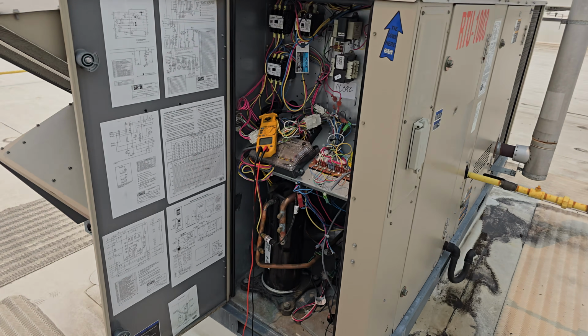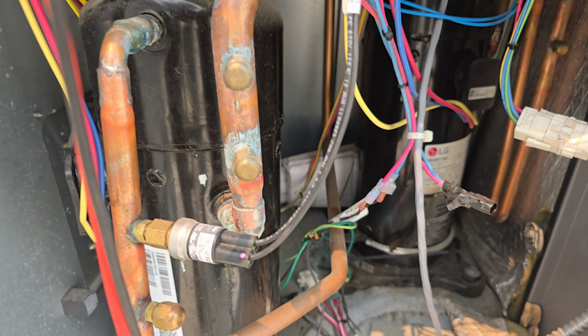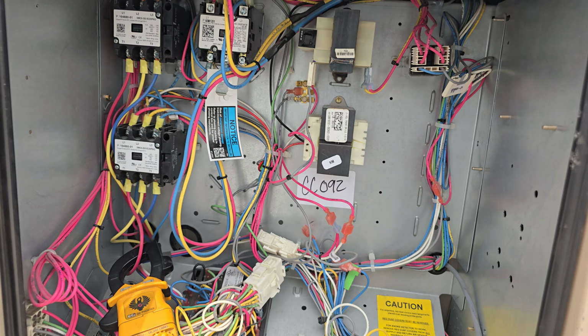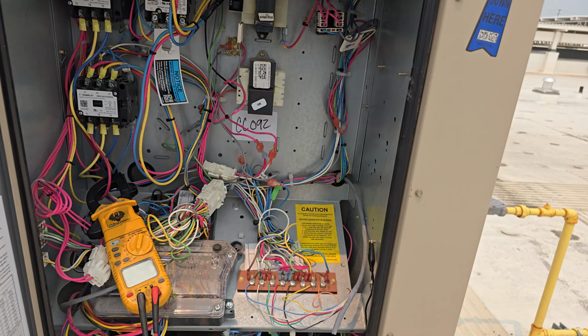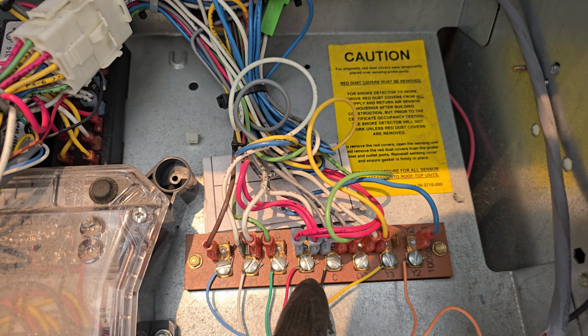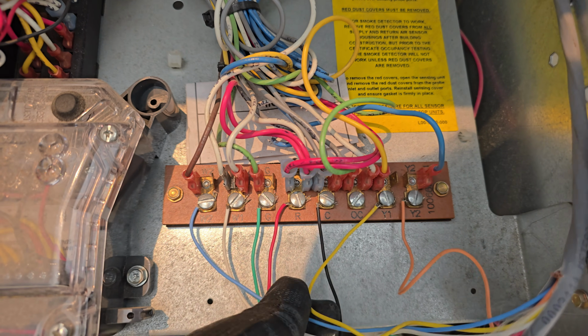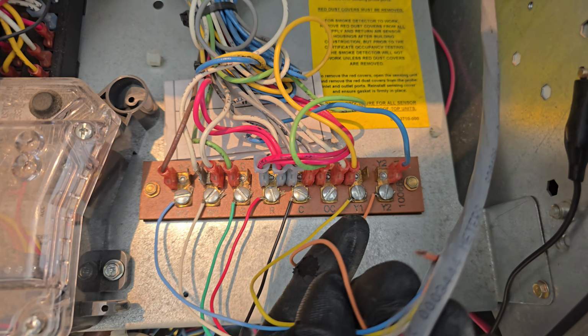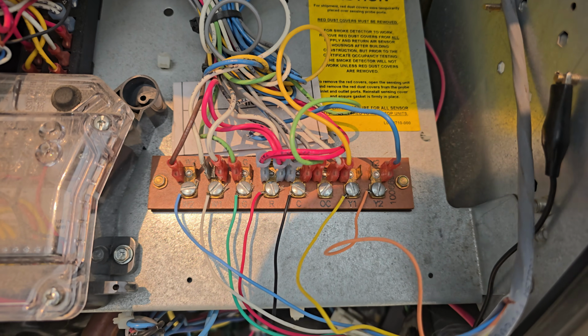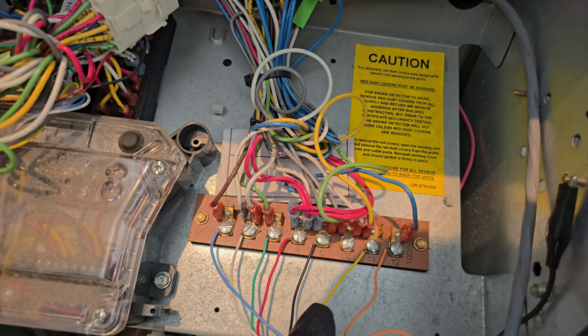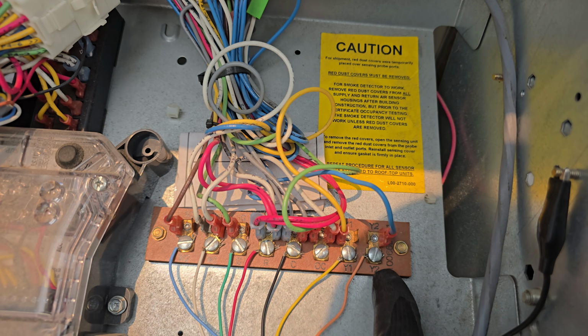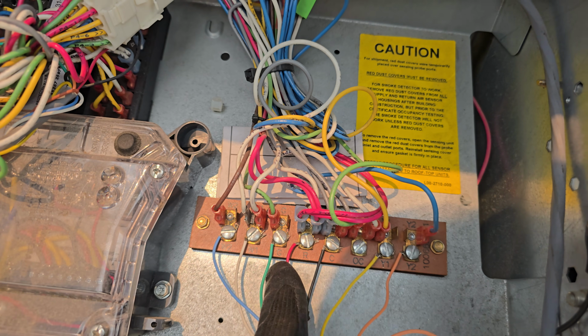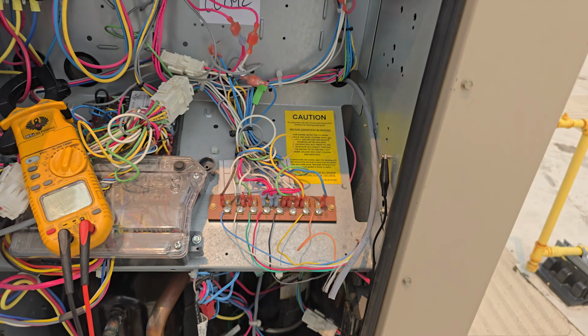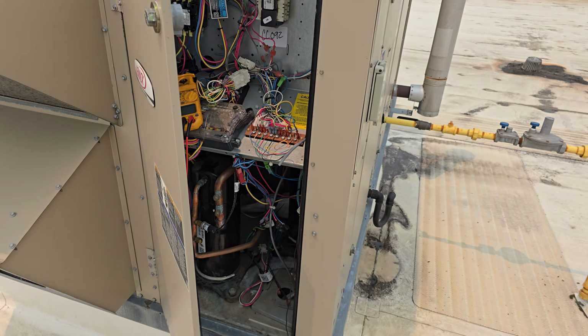Okay, after thorough checking, I did not see anywhere it is going to ground, and I turned on the unit. Again, it tripped off. So what I'm going to do is disconnect all this low voltage going to the thermostat. This is my wire going to the thermostat. I don't know if there's any crack or pinch on the wire going to the thermostat. So I'm going to disconnect this, and I will put a jumper between my Y1, Y2, my R and my G to bring in the cooling and see if that works. Okay, I'll keep you posted.